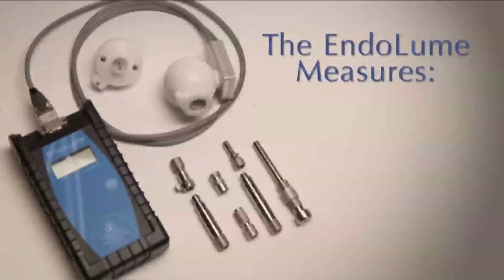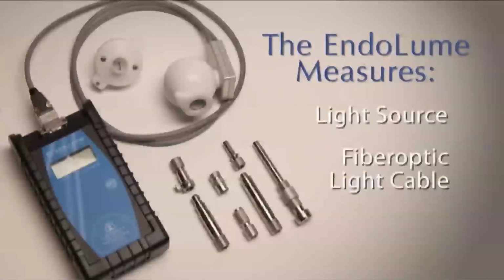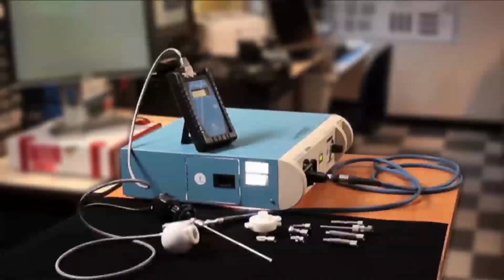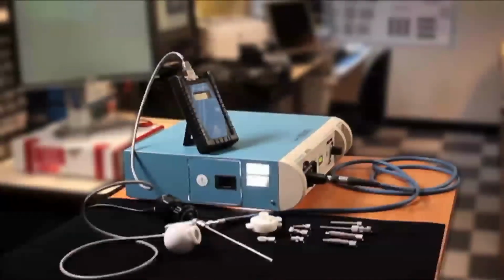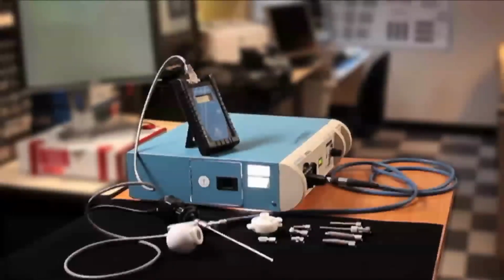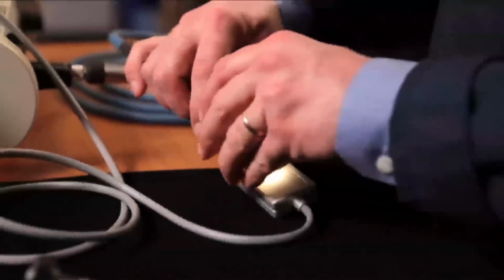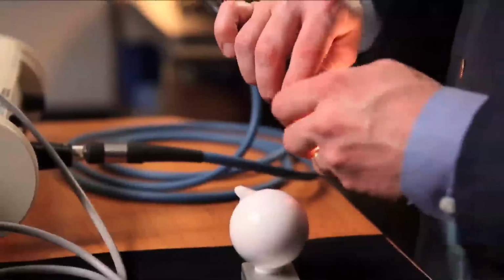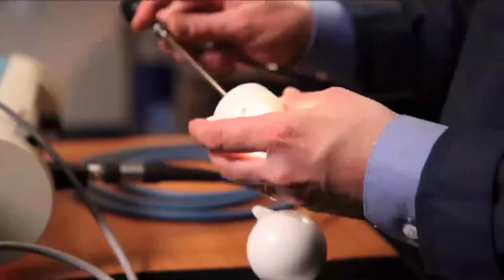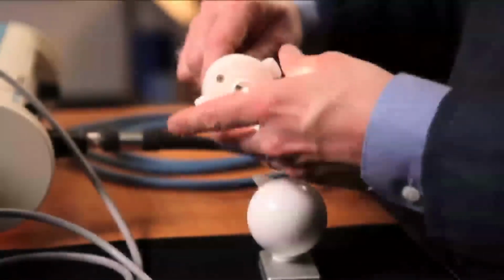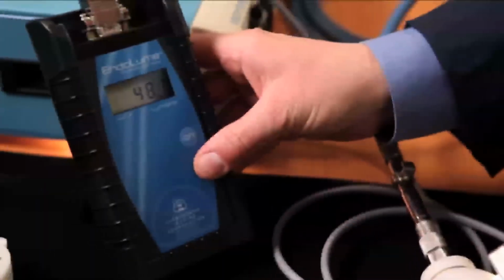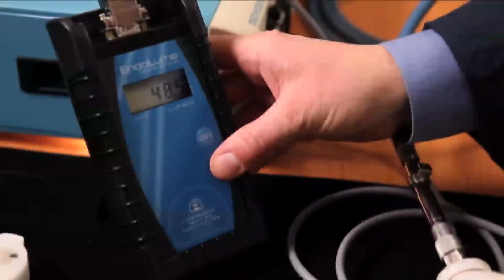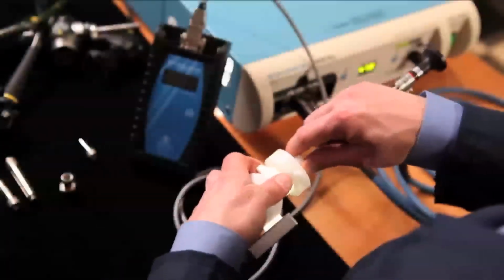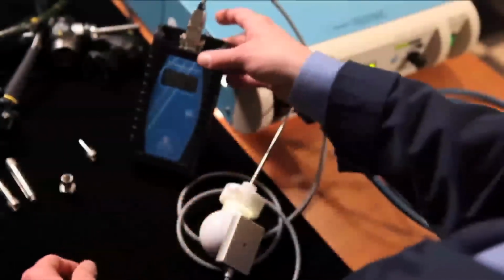The EndoLume directly measures the luminous intensity of the endoscopic light source, fiber optic light cable, and endoscope. The EndoLume provides more accurate results than any competitive device by directly measuring light output inside the light source where the light cable tip is positioned. Each of the components can be tested individually or together in an easy three-step approach for diagnosing the entire endoscopic illumination chain. The EndoLume accurately quantifies the light level that the surgeon will ultimately view on the video monitor time after time.